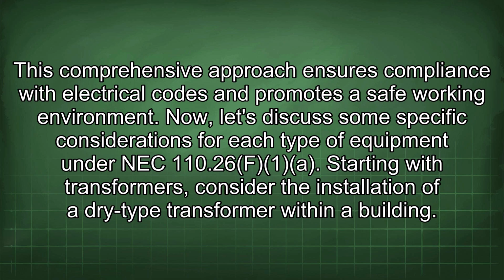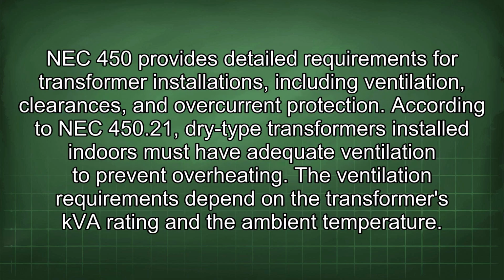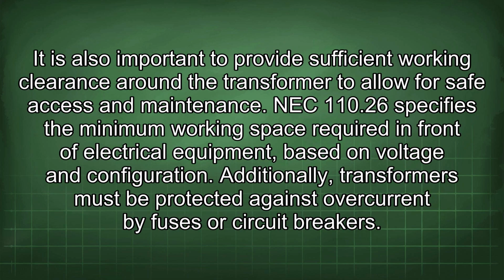Starting with transformers, consider the installation of a dry-type transformer within a building. NEC 450 provides detailed requirements for transformer installations, including ventilation, clearances, and overcurrent protection. According to NEC 450.21, dry-type transformers installed indoors must have adequate ventilation to prevent overheating. The ventilation requirements depend on the transformer's kVA rating and the ambient temperature. It is also important to provide sufficient working clearance around the transformer to allow for safe access and maintenance.